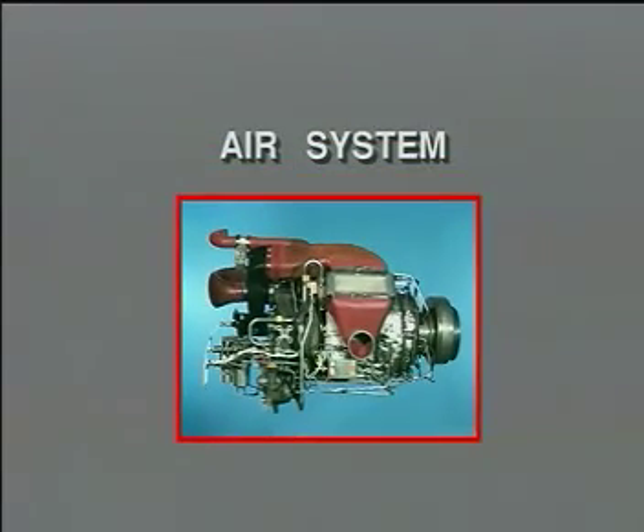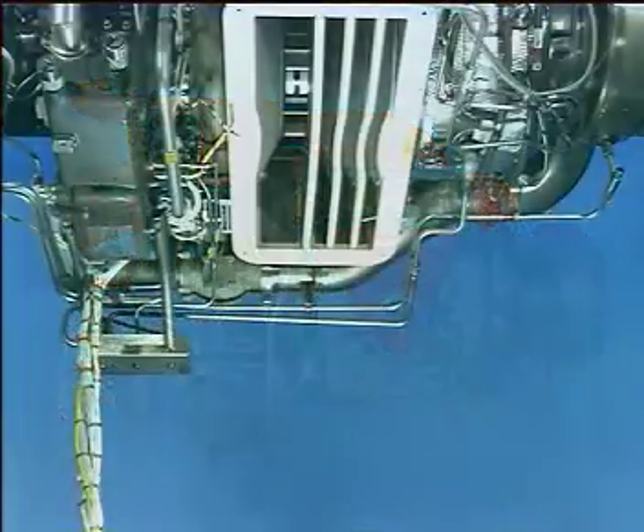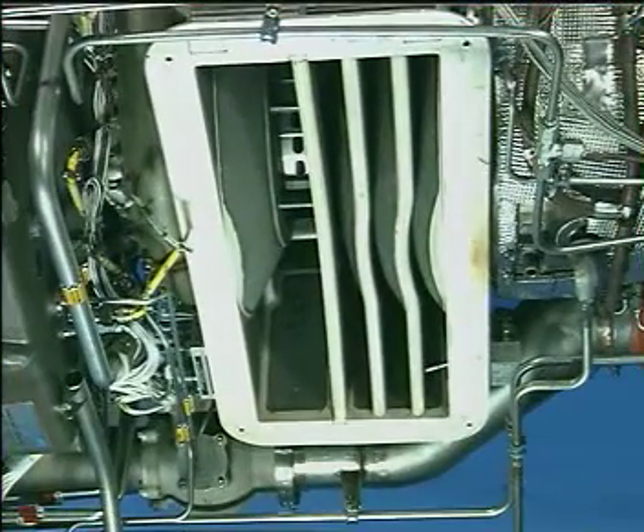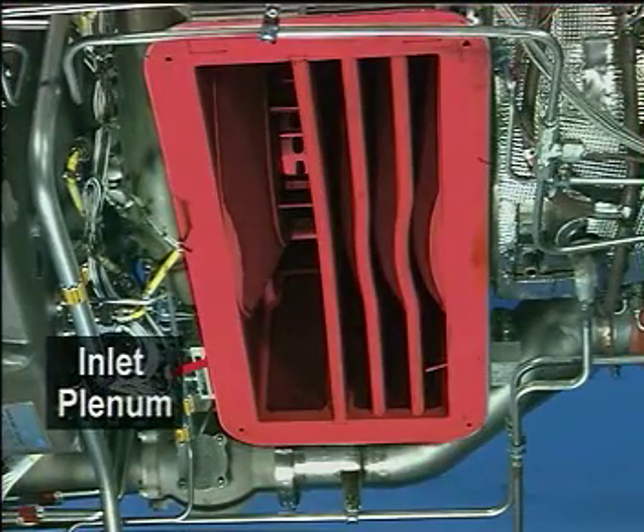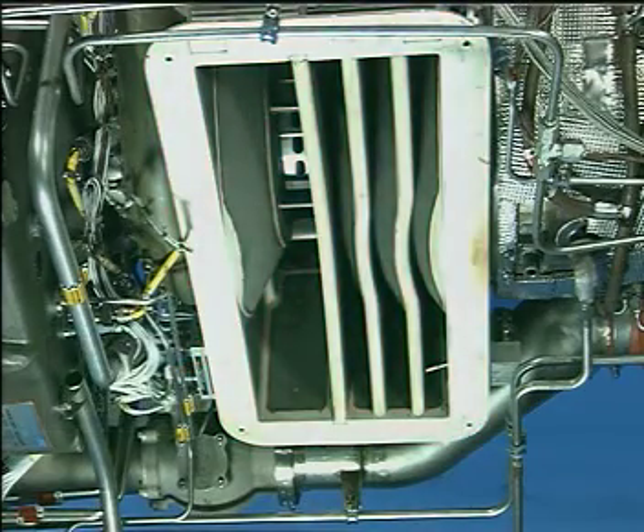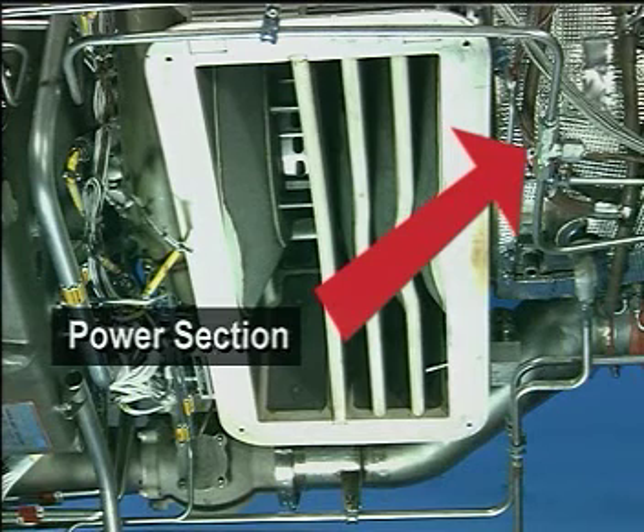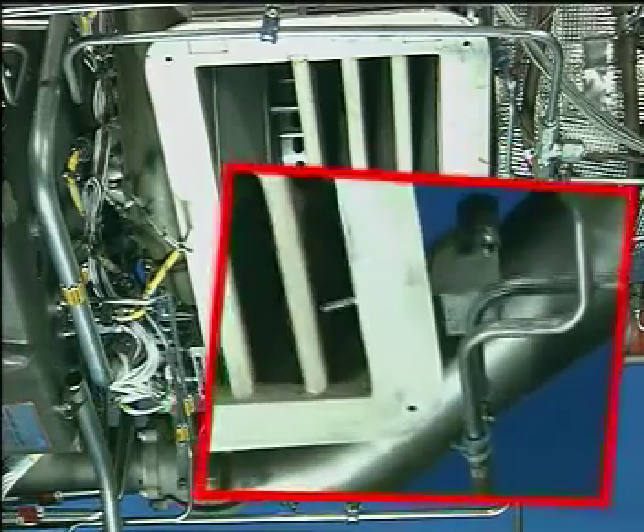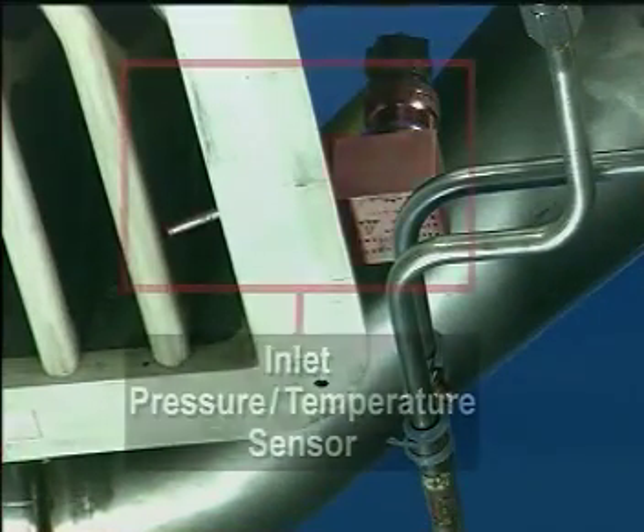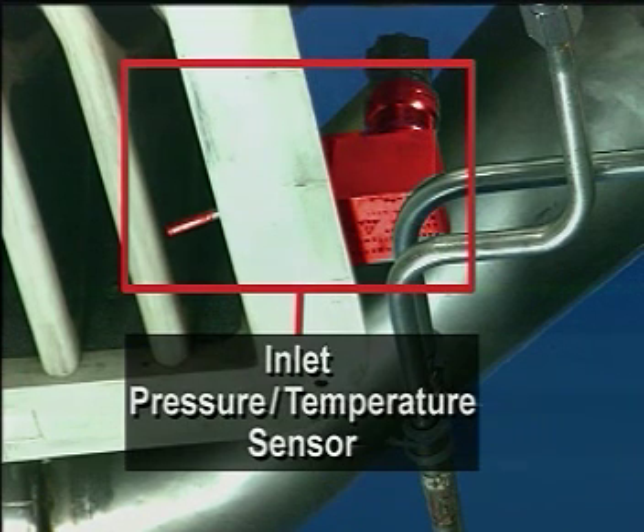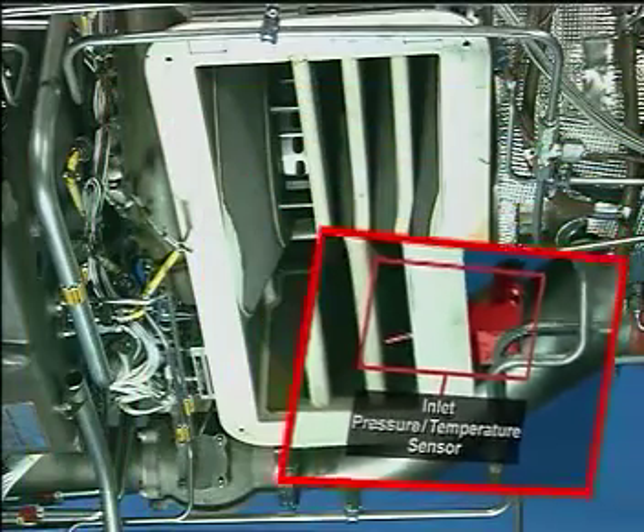Air system. The air inlet plenum supplies air to the power section compressor, the load compressor, and the gearbox fan. The airflow to the power section is used for combustion, oil system pressurization, and to operate the APU compartment cooling valve. The airflow is monitored by the load compressor inlet pressure temperature sensor installed on the rear of the air inlet plenum near the 3 o'clock position. The data is used for fuel metering control.